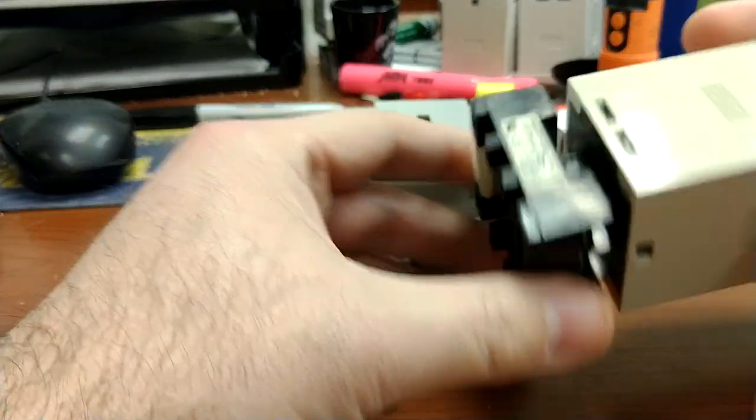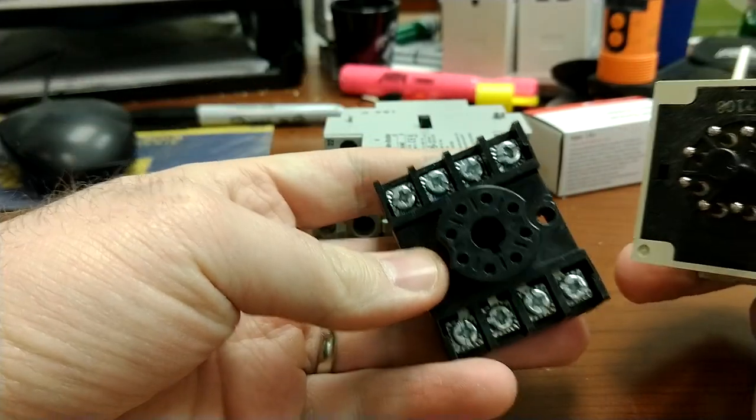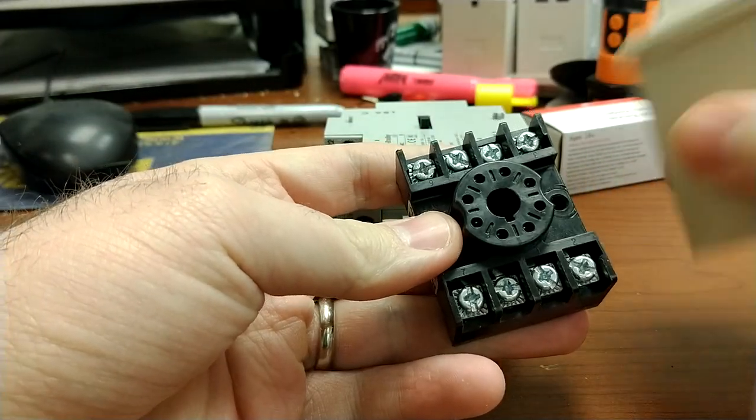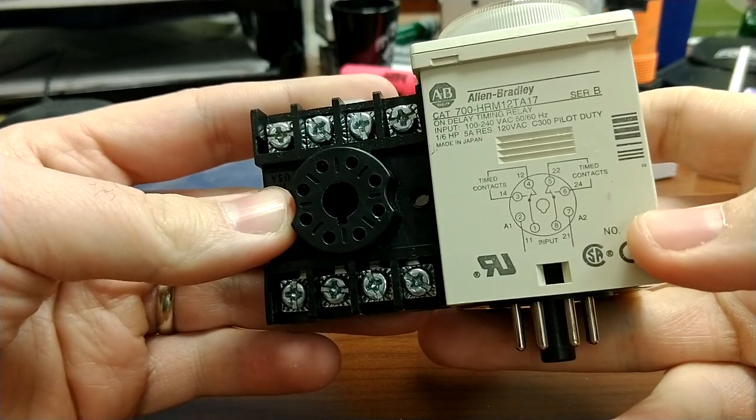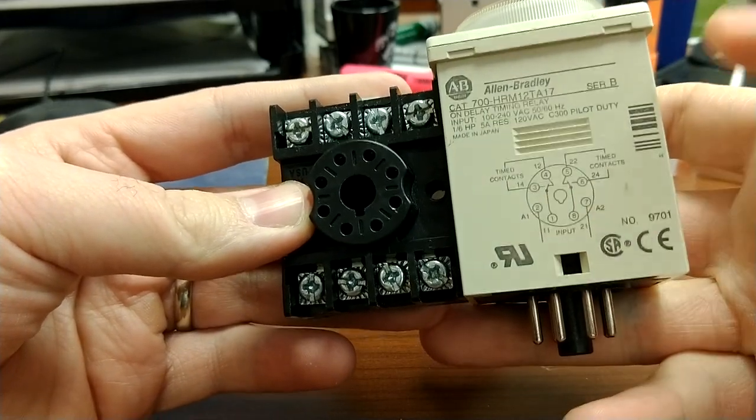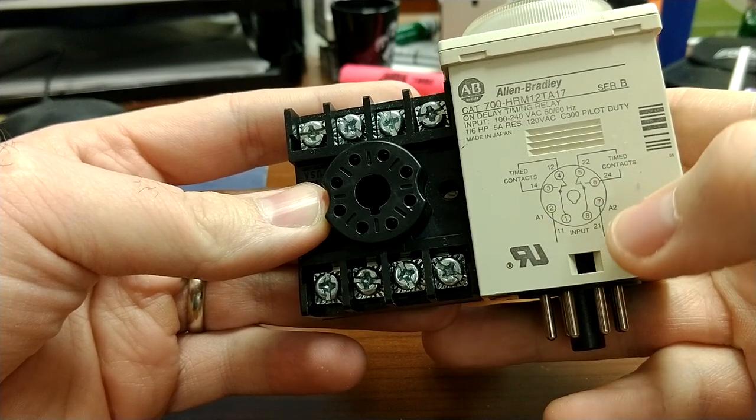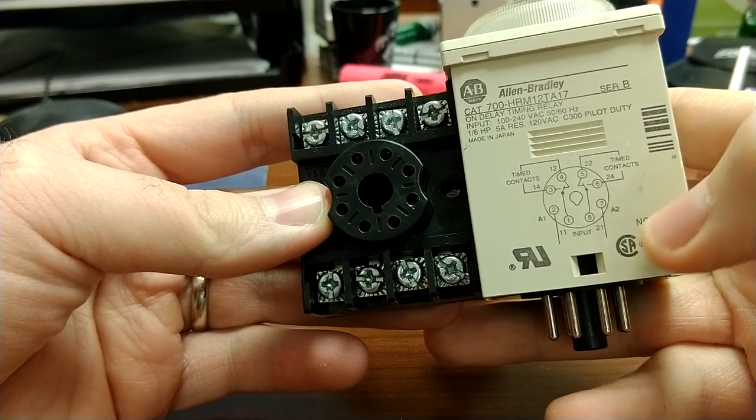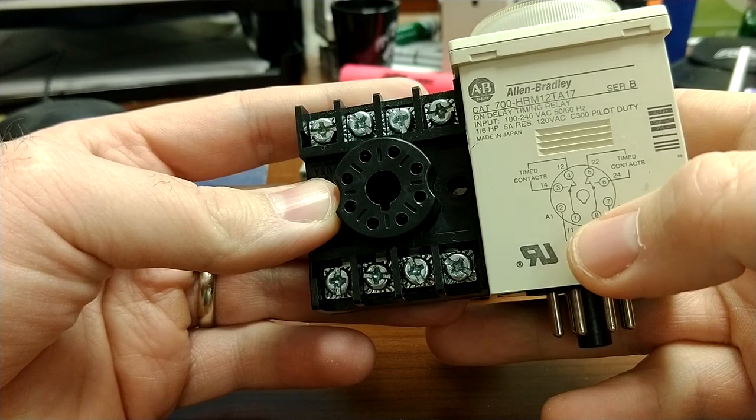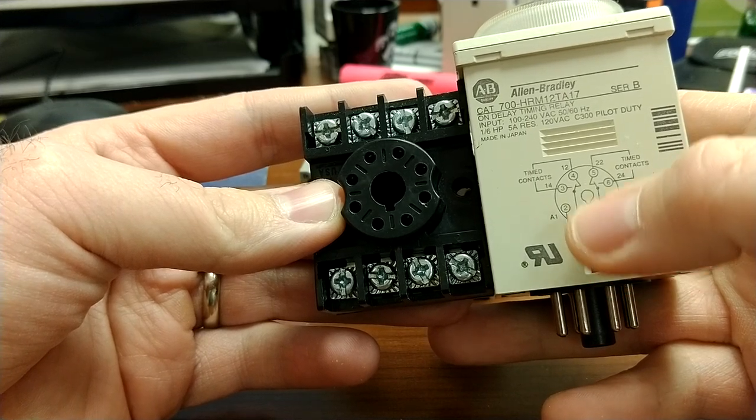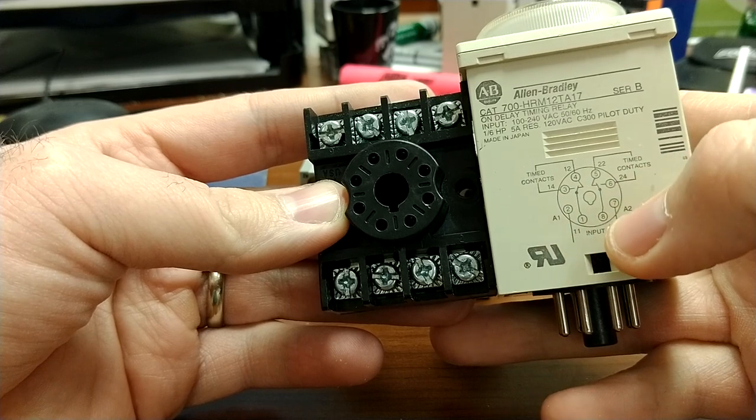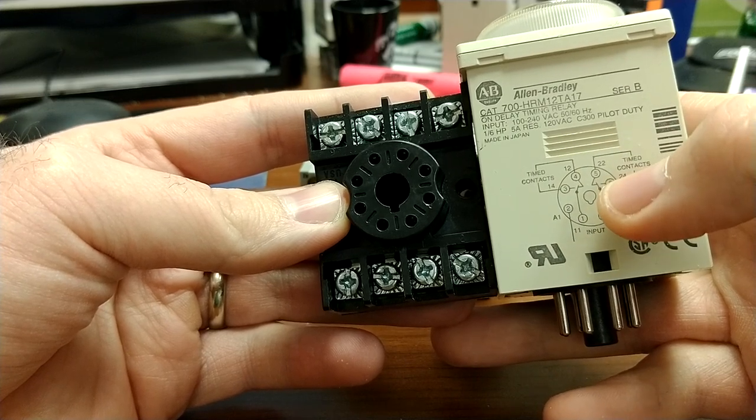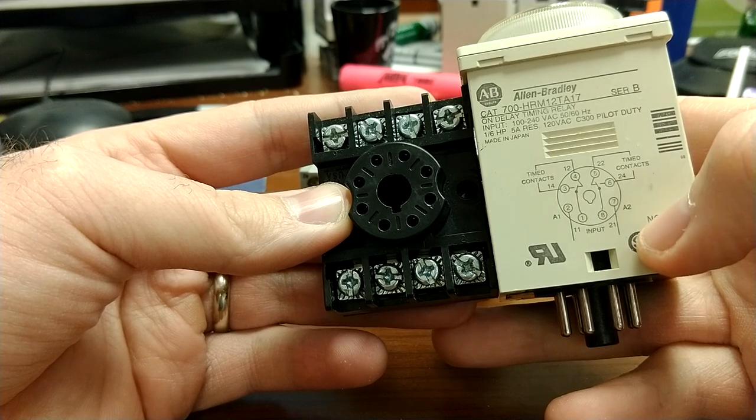With relays, you can see here there's a base that you take off and everything wires into here, and if you read the side of a relay, you can then see how it's supposed to be wired. Now, this is a timer, but you can see my A1, A2, that would be my coil, and the 11 would be my common for my relay, and then 12, 14. In this case, it's a timed open-time closed setting, or you're normally open, normally closed.